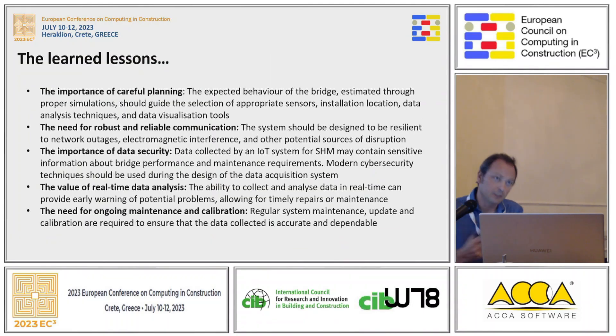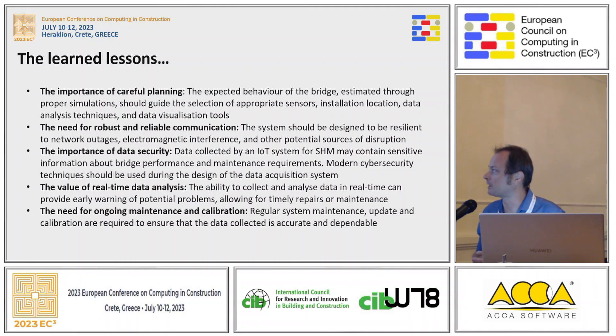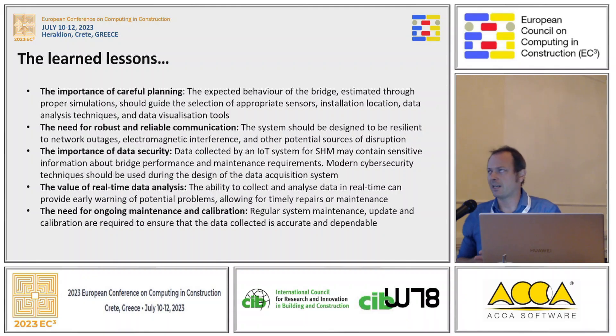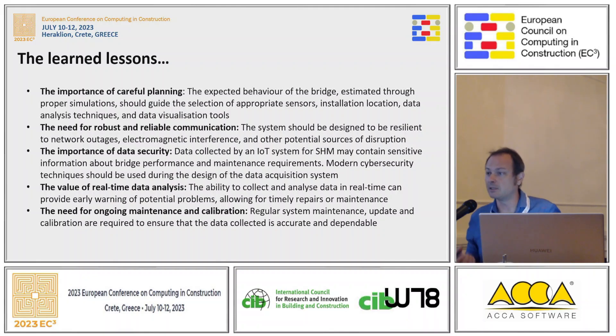In conclusion, what we learned from our practical experience: it is very important to carefully plan the installation of sensors inside the bridge; there is a need for a robust and reliable communication system; data security of the data transmitted from the system to the data collection platform is important; real-time data has significant value; and there is a need for a regular system to maintain the quality of the data generated by the sensors installed on the bridge.